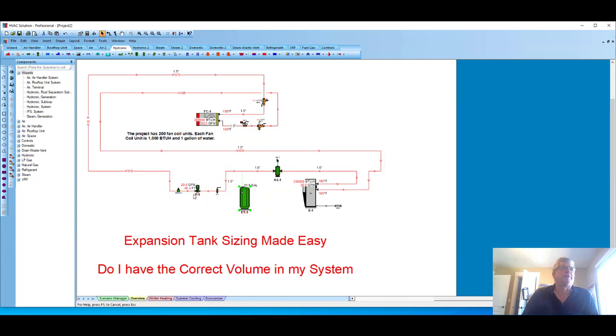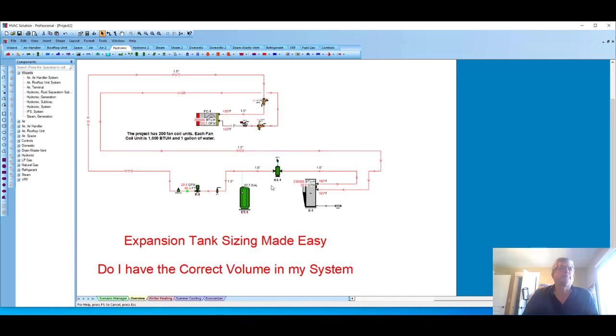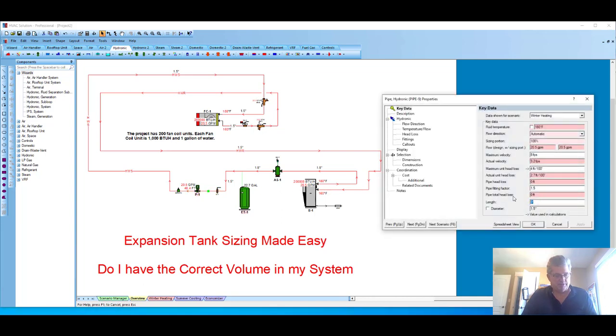So to get the pipe in the system, I'd look at the pump and take it all the way out to the load, and I'd come in that piece of pipe right there, and I'd say, that pipe is 100 feet long. We have a fitting factor of 50%, so it's going to take a little bit more, right? 150. You could change that to 1.2 or whatever. And then I'm going to do the same on the return. How far return piping do I have? I'm going to come right in here, select that as well. Maybe that was 150 feet of pipe.